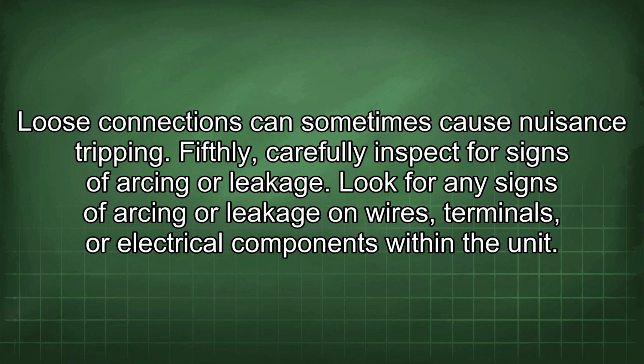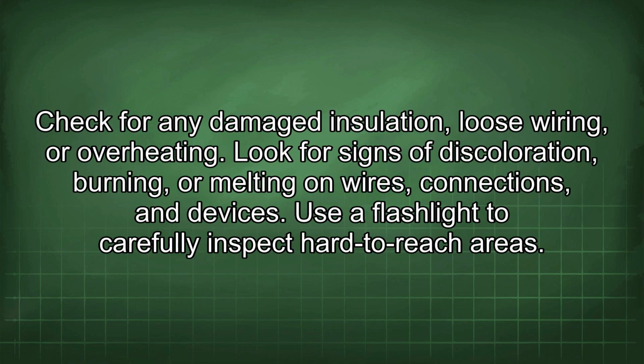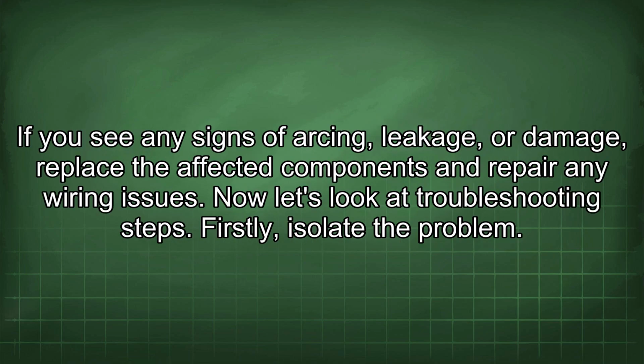Fifthly, carefully inspect for signs of arcing or leakage. Look for any signs of arcing or leakage on wires, terminals, or electrical components within the unit. Check for any damaged insulation, loose wiring, or overheating. Look for signs of discoloration, burning, or melting on wires, connections, and devices. Use a flashlight to carefully inspect hard-to-reach areas. If you see any signs of arcing, leakage, or damage, replace the affected components and repair any wiring issues.